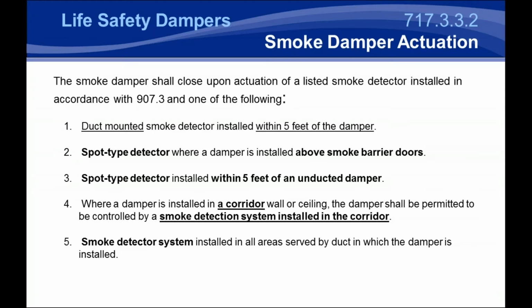As you can imagine, a fire damper can only have a sleeve so long, and because of that, there's only so much room we can mount that smoke detector and all of the other boxes and electrical connections needed to make sure that damper will operate correctly. Because of that, a lot of times if we mount smoke detectors from the factory, you'll have actuators, boxes, and a smoke detector potentially on 2 or 3 sides of the damper.